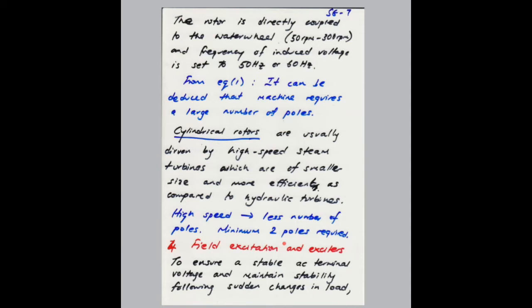The fourth section is looking at the field excitation and exciters that we use in synchronous machines. So they ensure a stable AC terminal voltage, right? Remember the current that is passing in the rotor circuit produces the magnetic field in the air gap, and that's sweeping your conductors on the stator side. And if you have a control system fitted on your excitation circuit, which is your main exciter circuit, that will enable you to vary the rotor current, the field current, and hence vary the voltage that's being induced on your stator side, right? So by having this control circuit, we ensure that a stable voltage is maintained.